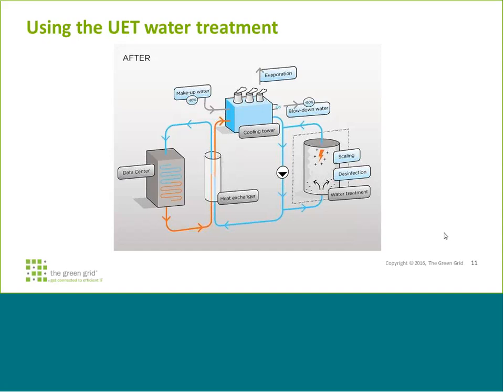What we started off by doing is reduce all the scaling that had been formed in the cooling tower and on the heat exchanger plates already. So not only did we save a lot of water, we actually made the system cleaner than it ever was before. We could see that on the mass balance. We did see a disbalance in the chlorides and the calcium, and it was explained by the fact that we actually cleaned up the system, and currently the system is clean, so we have reduced the power to the system to compensate, otherwise the water would be a bit aggressive. So okay, we can play with it.